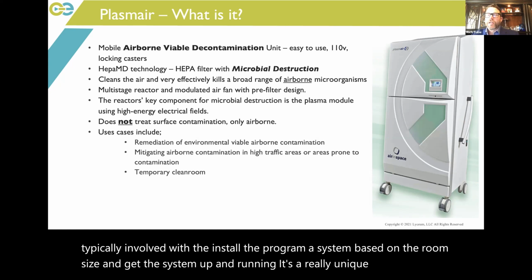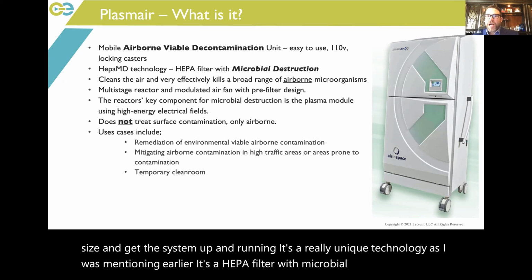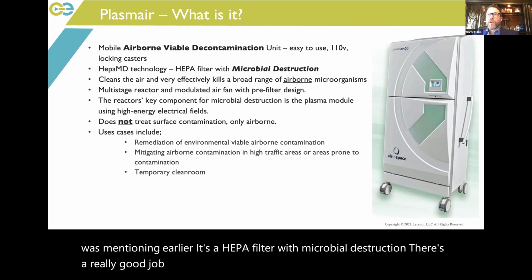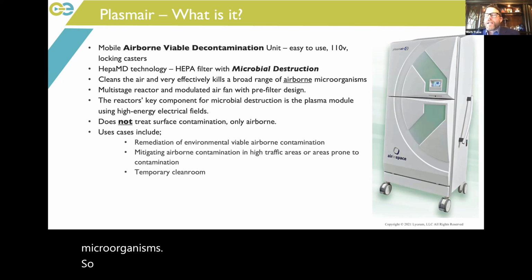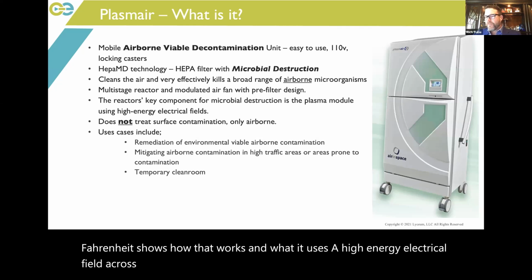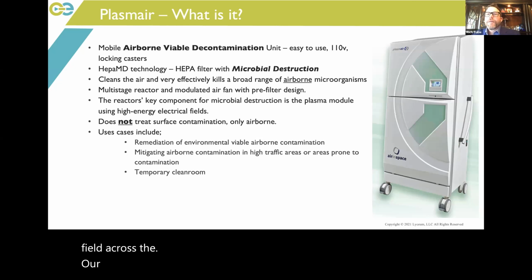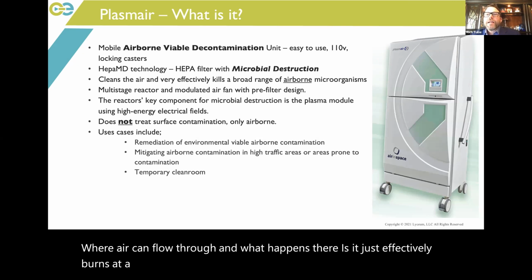As I was mentioning earlier, it's a HEPA filter with microbial destruction. Does a really good job of killing any type of airborne microorganisms. So it's a multi-stage reactor, and I have a diagram in the next slide that shows how that works. And what it uses is a high energy electrical field across the plenum where air can flow through. And what happens there is it just effectively burns at room temperature all the microorganisms.